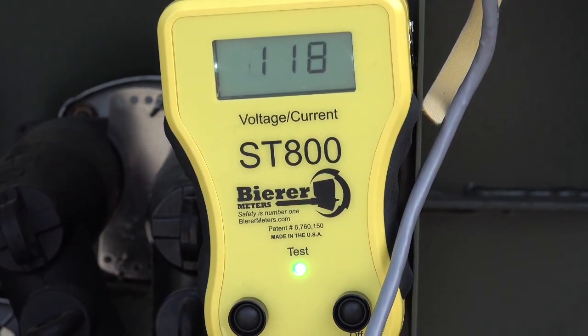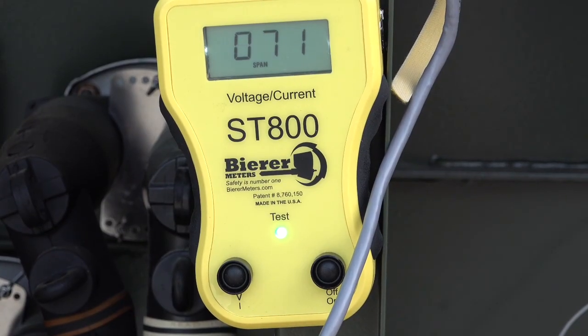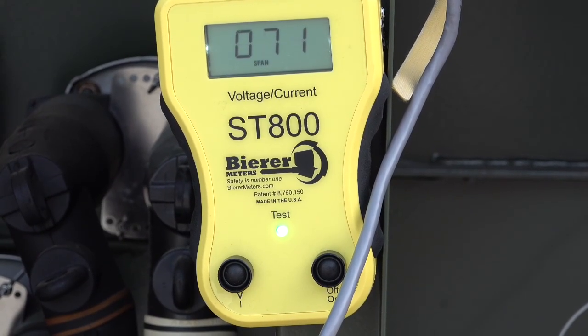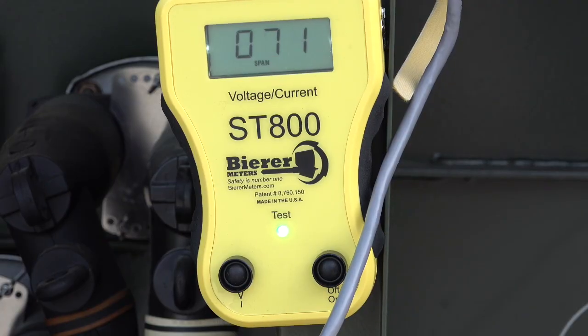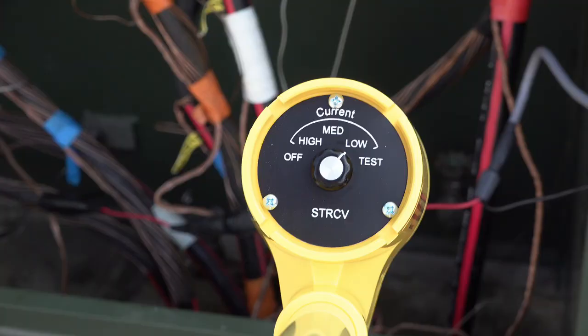Allow the unit enough time to ramp up and achieve 800 amps before we begin our testing. While conducting this test, since one of our leads is actually connected to the concentric of one of the primary cables, there are many paths to ground, so it is important to put the STRCV in the low current setting. This will allow the STRCV enough sensitivity to pick up the primary cable in a manhole or a ditch.